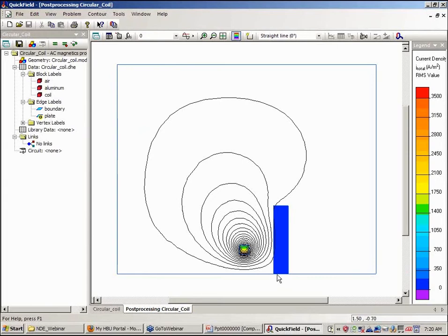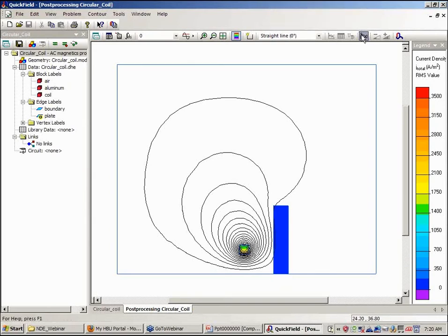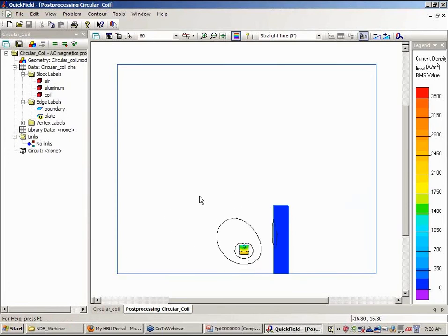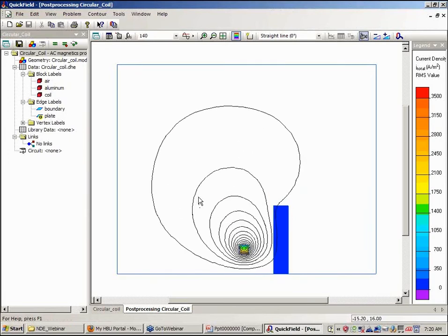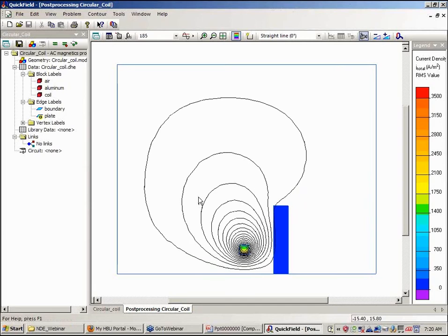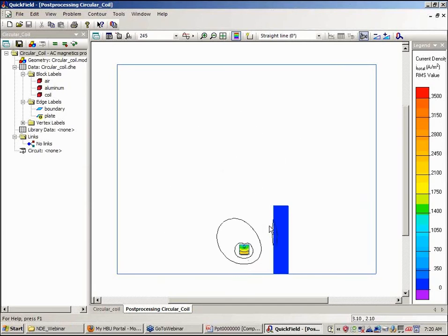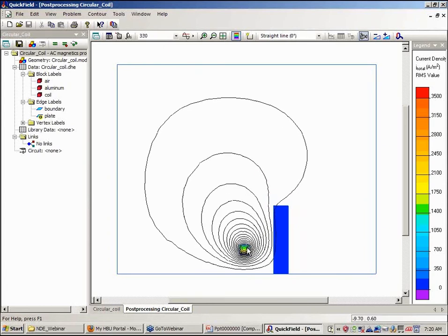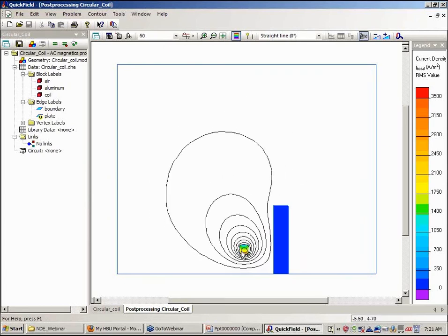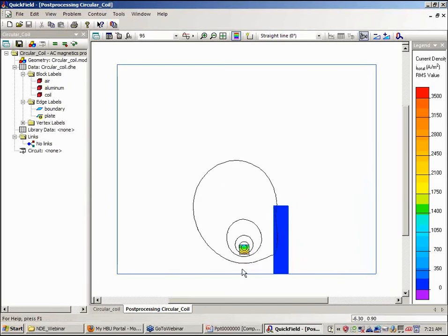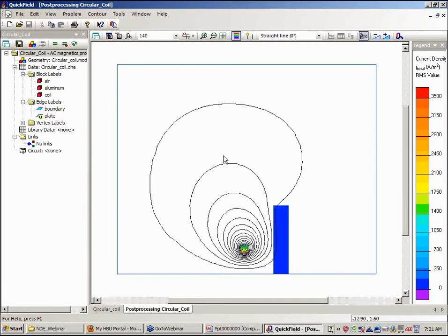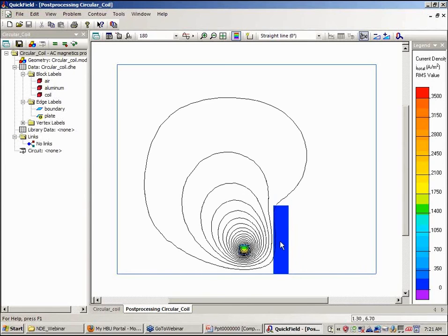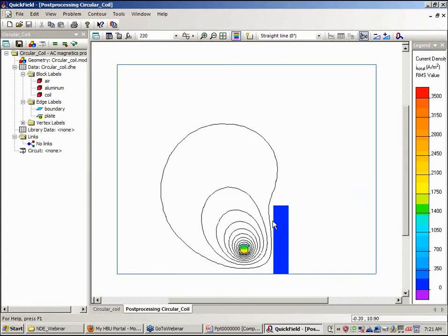So this is the eddy current density and the flux distribution. Once again we can animate the magnetic field. Now some of the magnetic field is generated by current that's flowing in the circular disk here. In fact, if you look at a phase angle of 90 degrees, then primarily the magnetic field will be due to eddy currents that are flowing in our object under inspection.